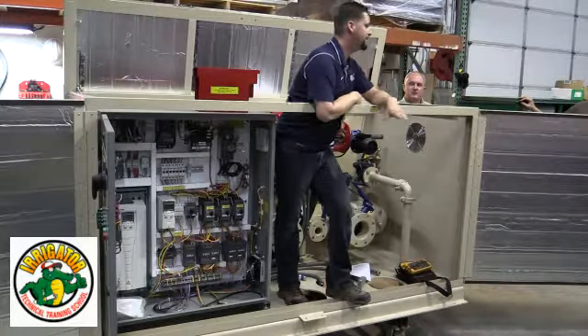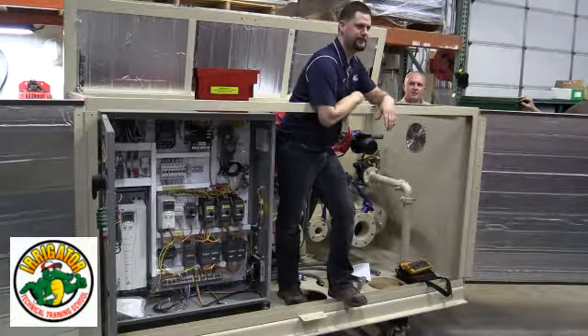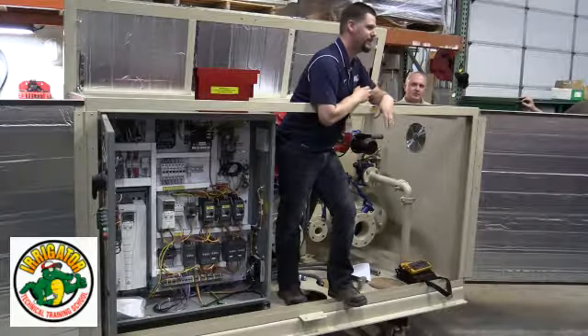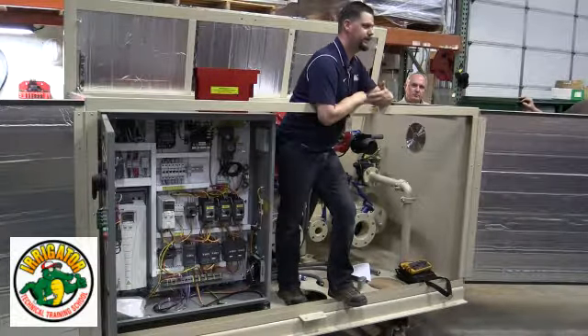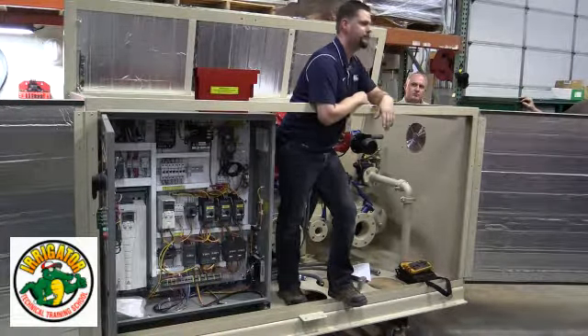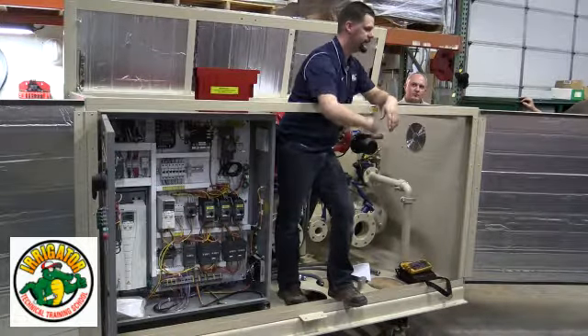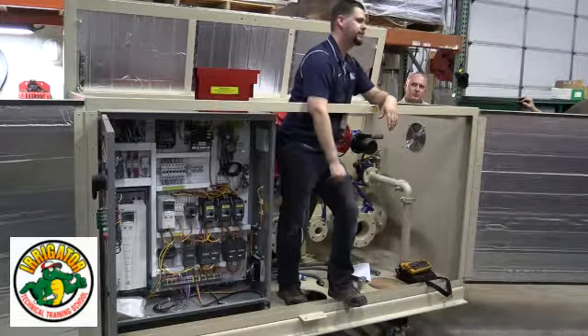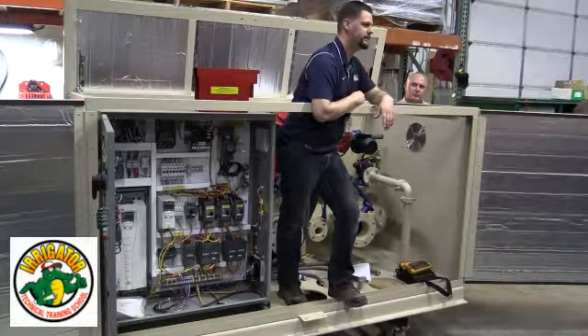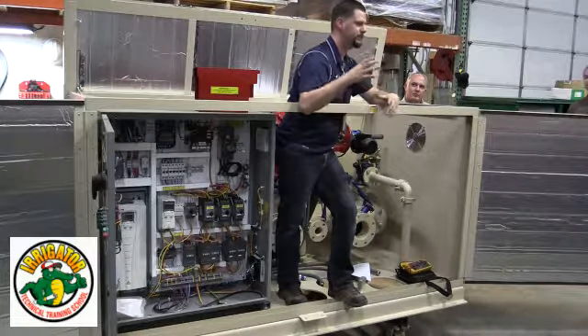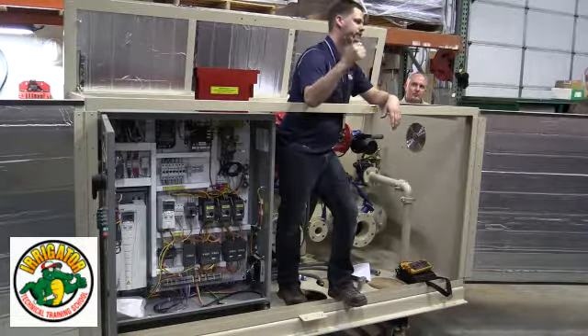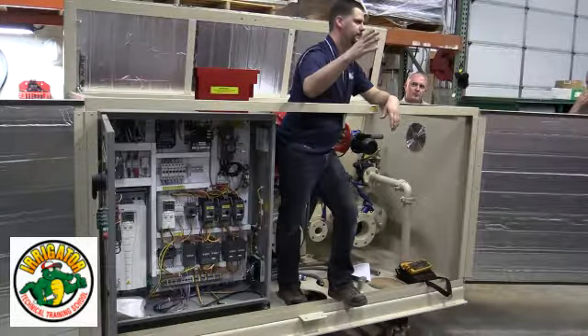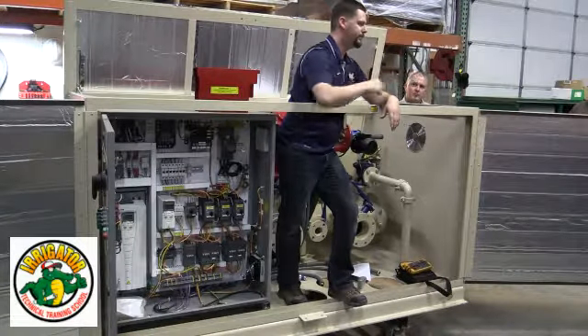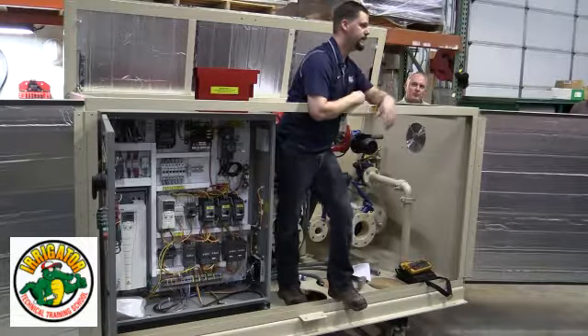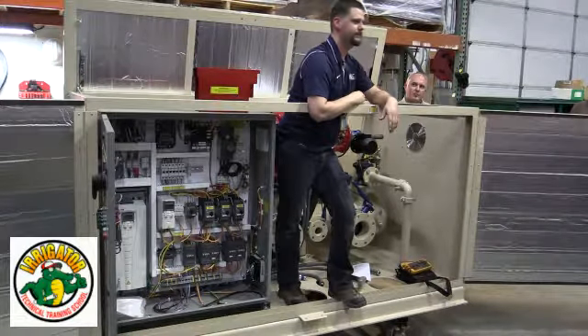So here's some troubleshooting for our startup class: if you ever end up at a job where their automatic filter won't flush, shut the isolation valve to their pump station and raise their set point. That will get as much pressure as possible after the filter without a bunch of flow, and will allow that pressure to basically vacuum the inside of the filter.